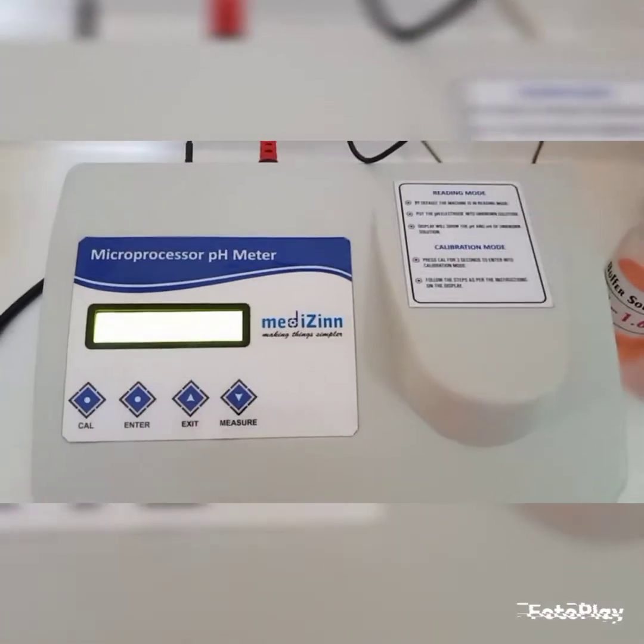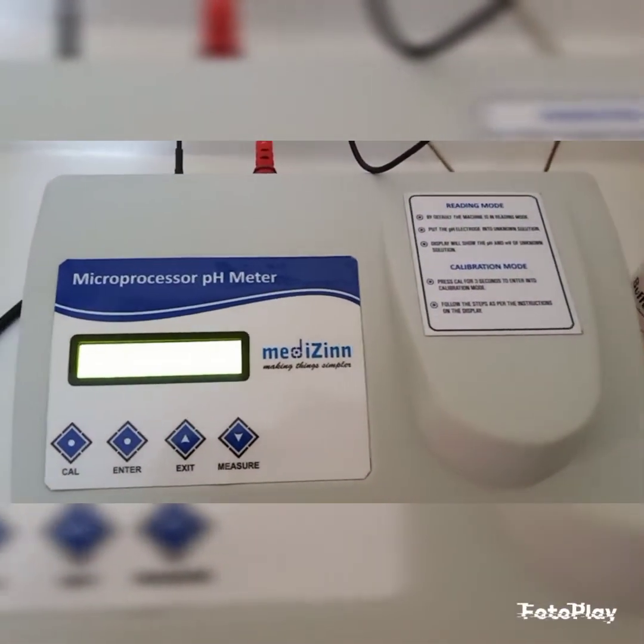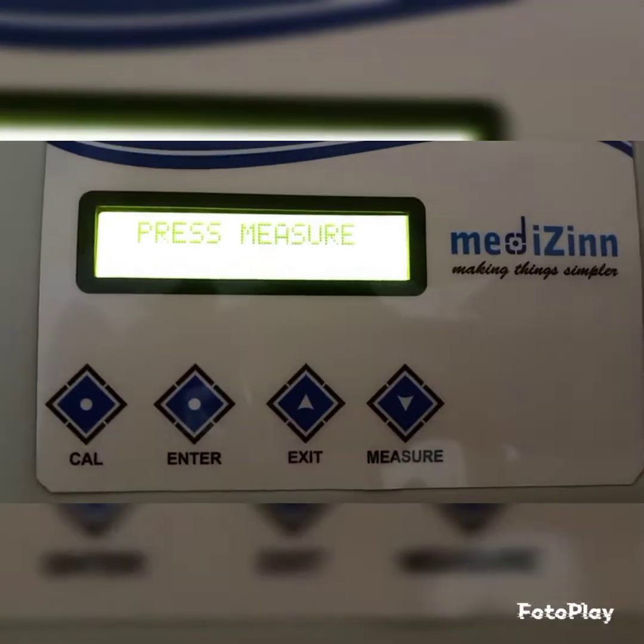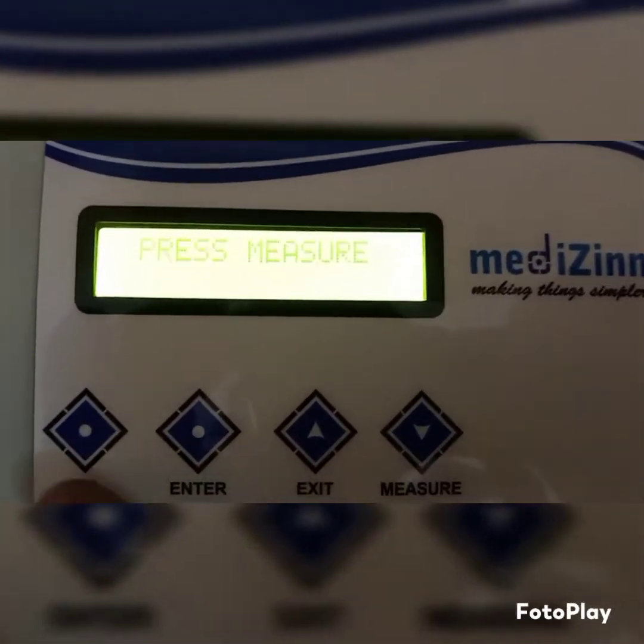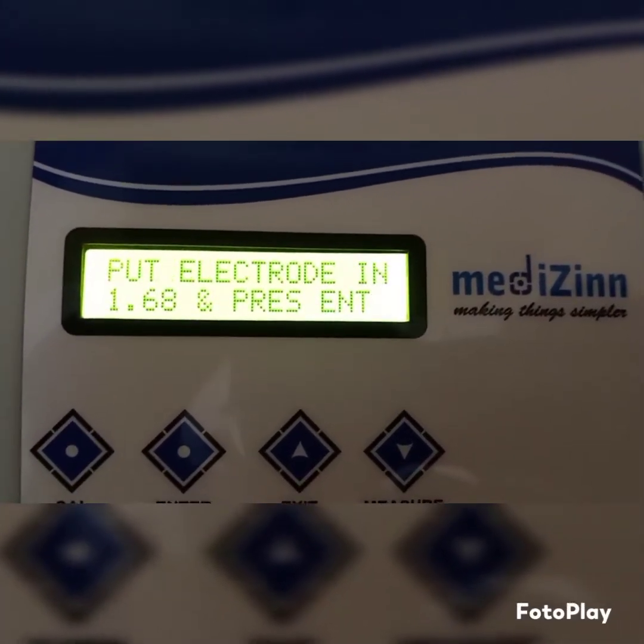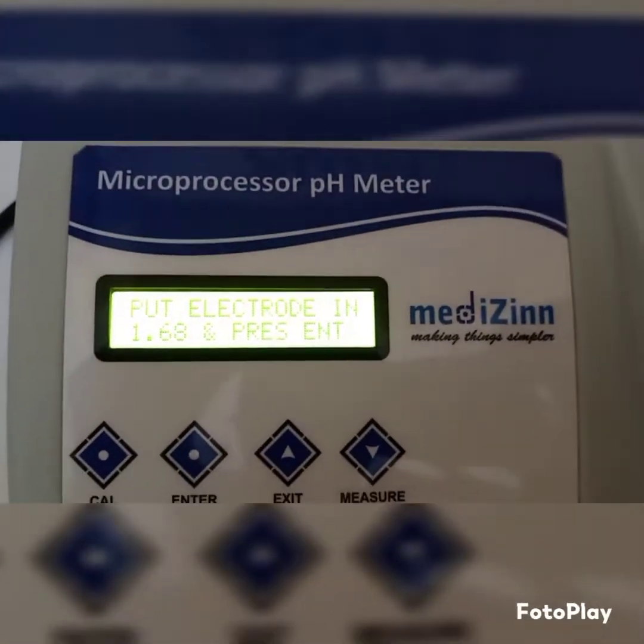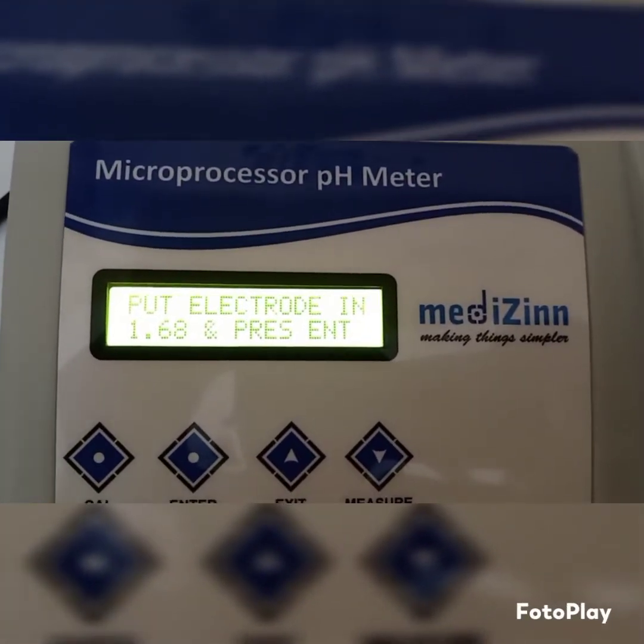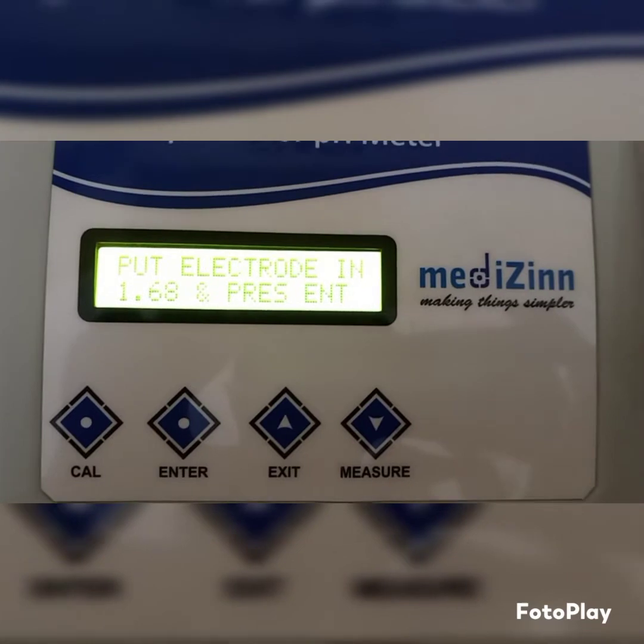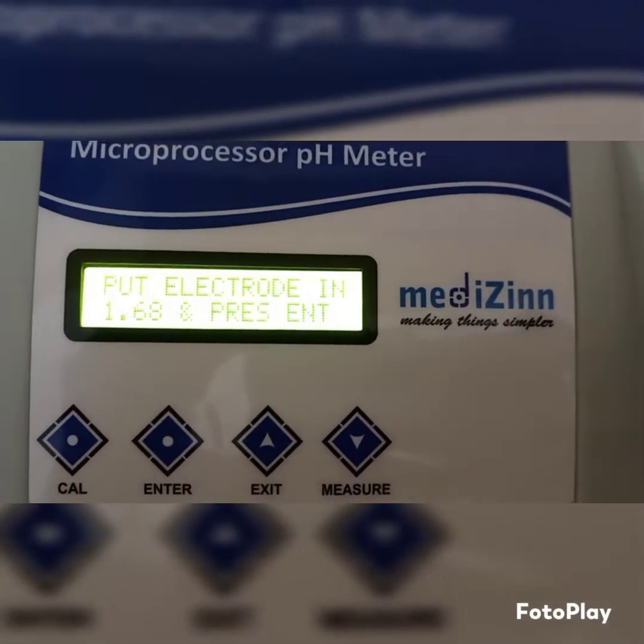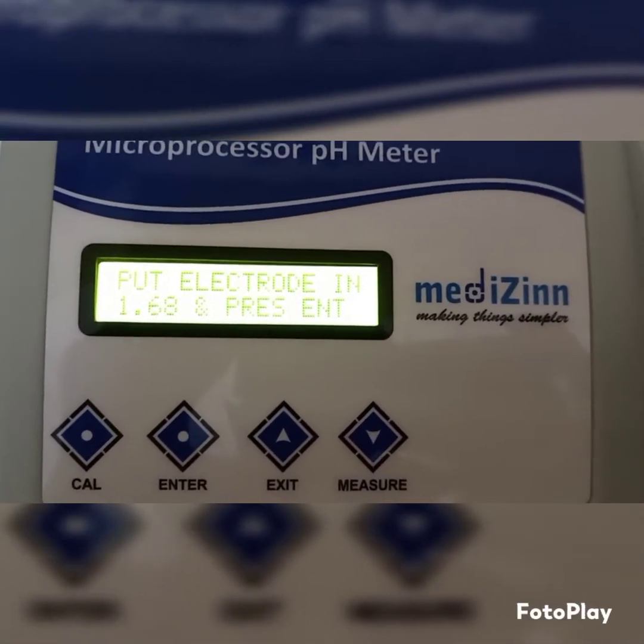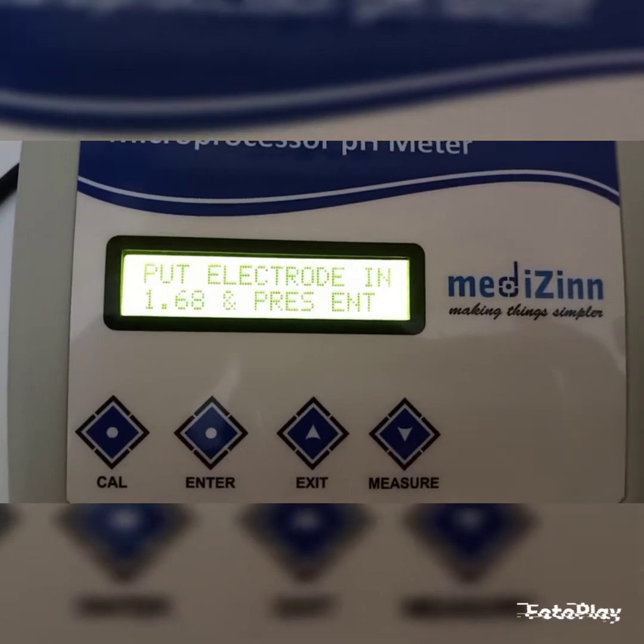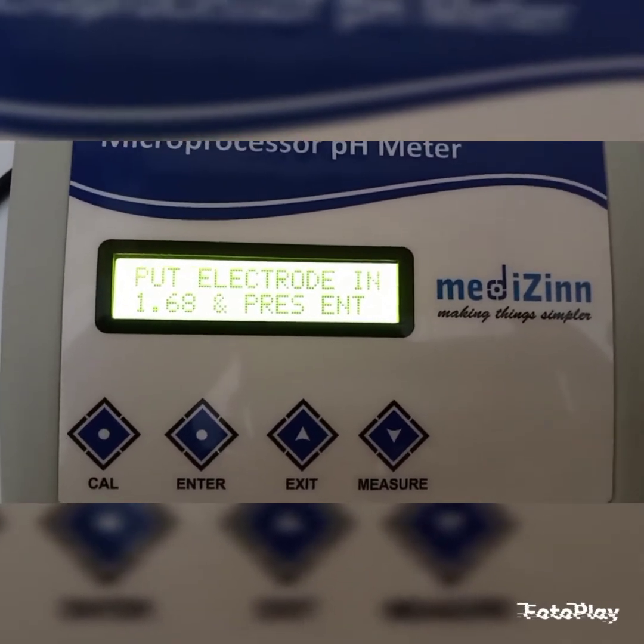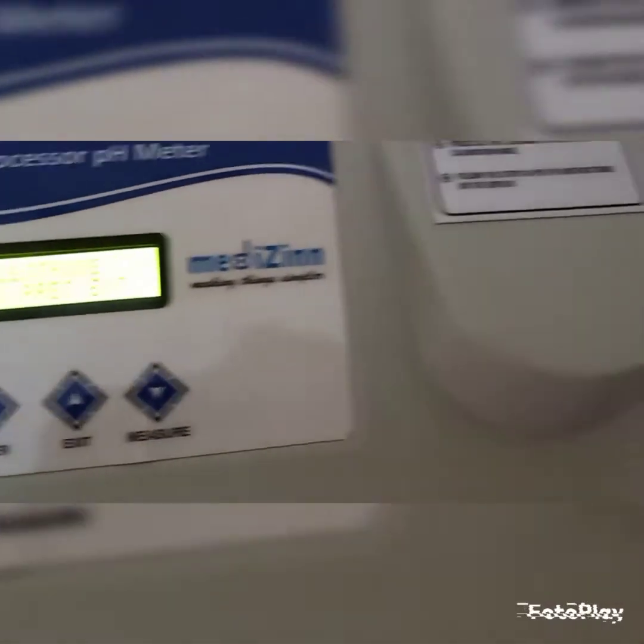So let's start the calibration process. For the calibration process, press Cal button. Display showing put electrode into 1.68 pH and press enter. So if user want to go for 3-point calibration, just press exit button. It automatically moves into 4 pH. So this is a 1.68 pH.